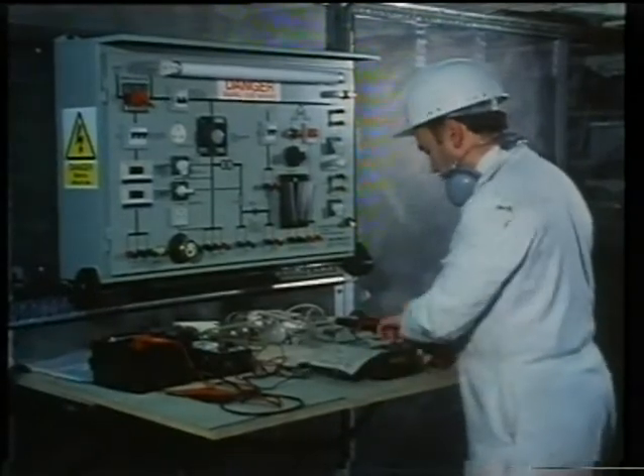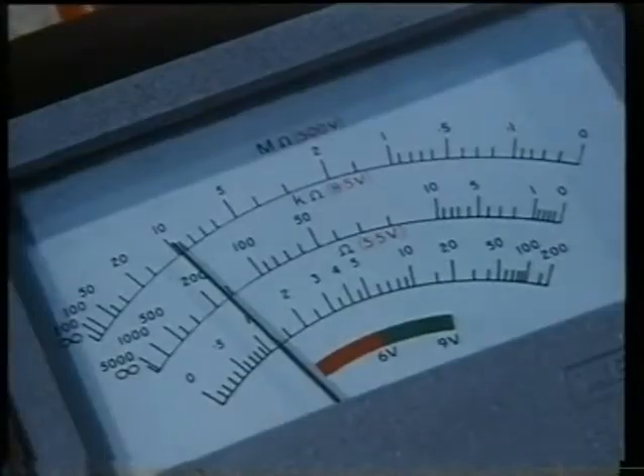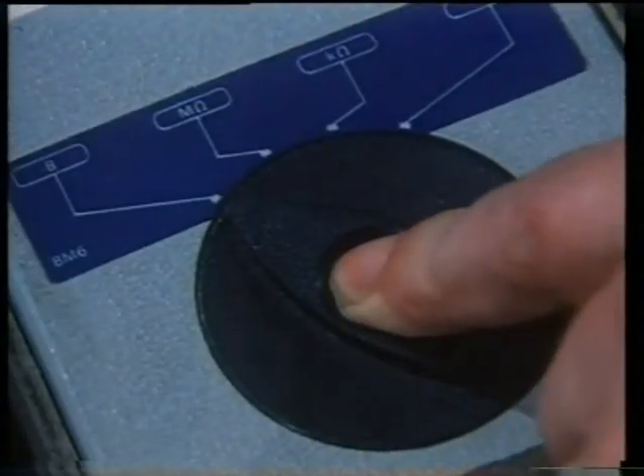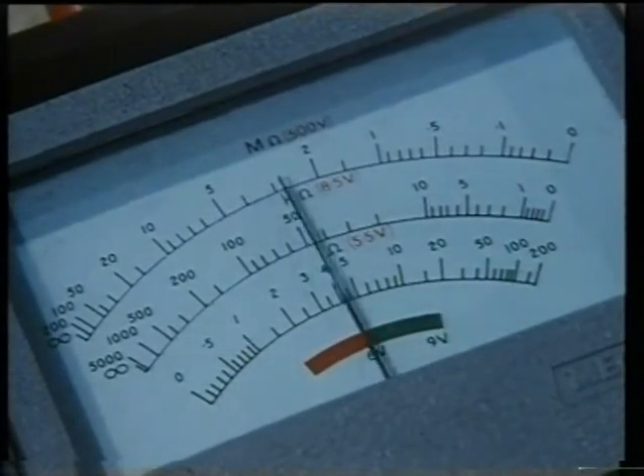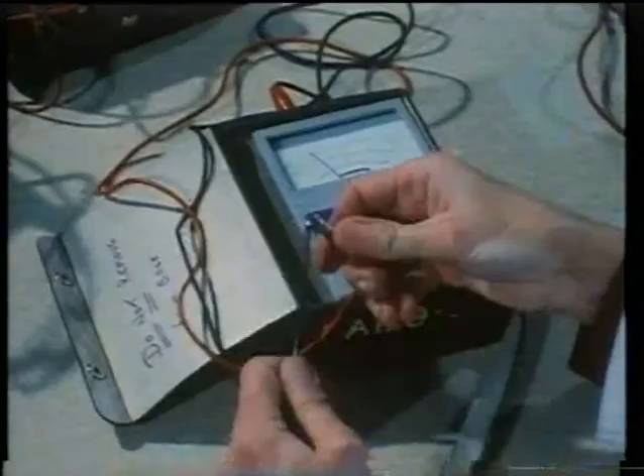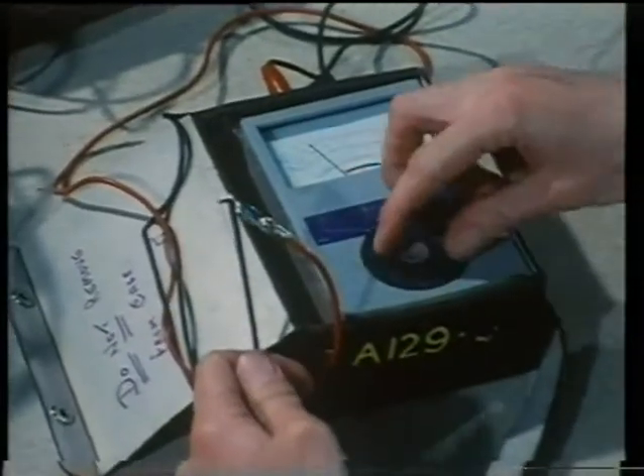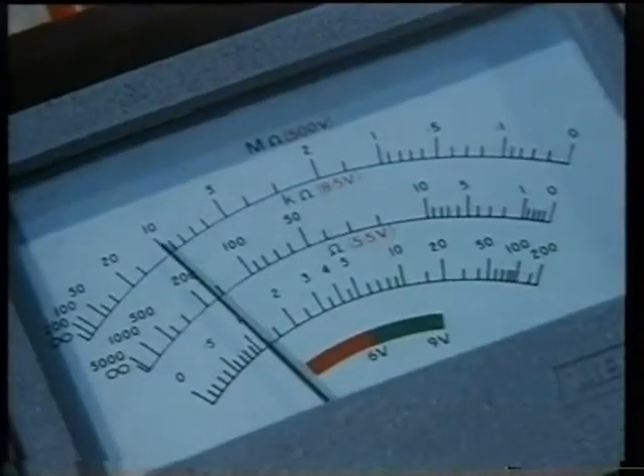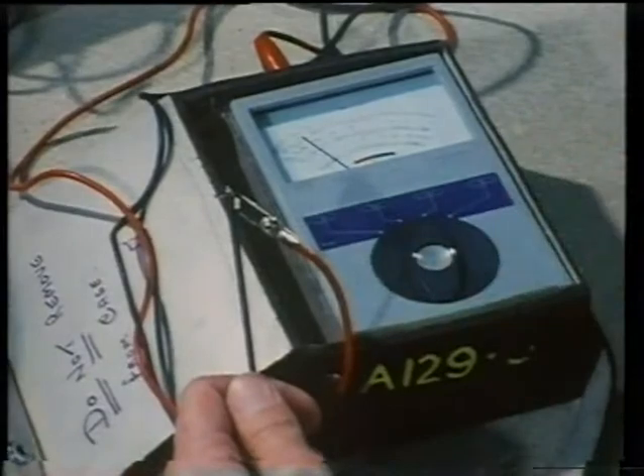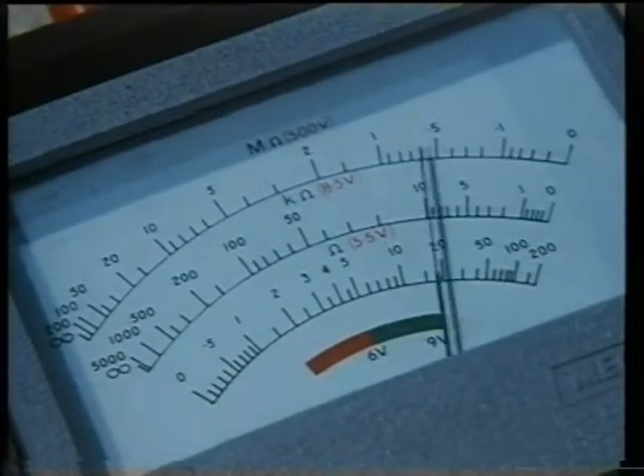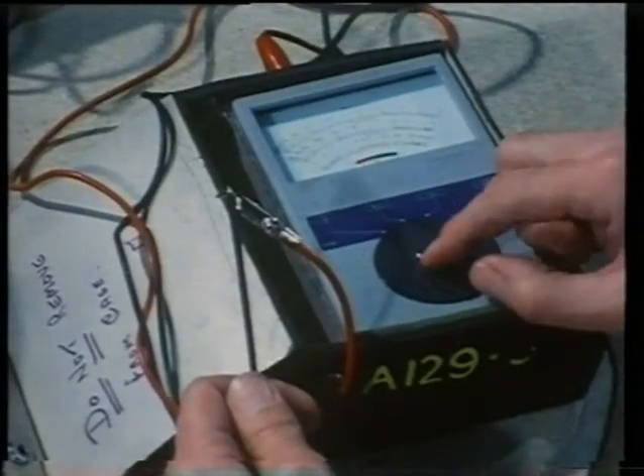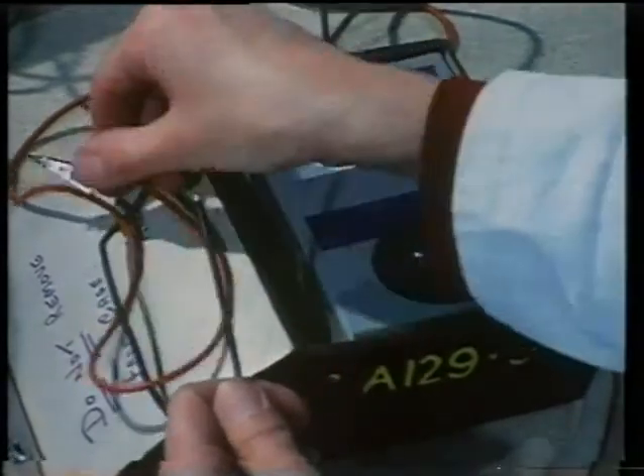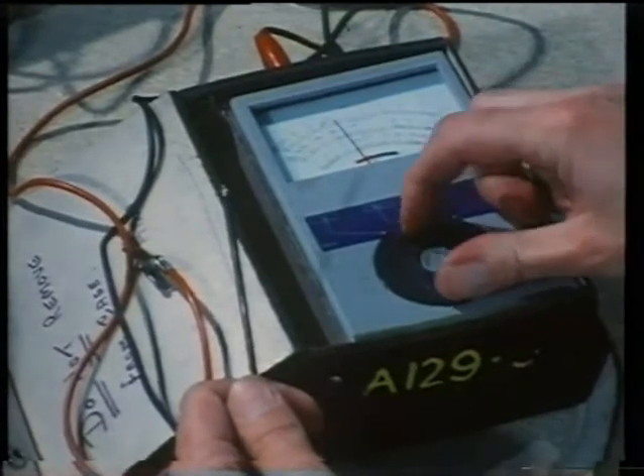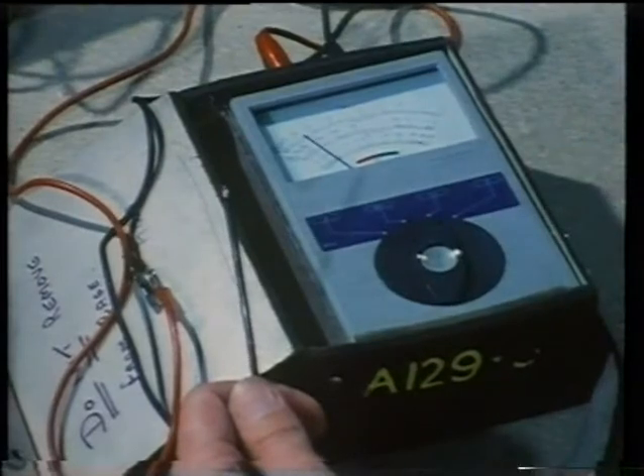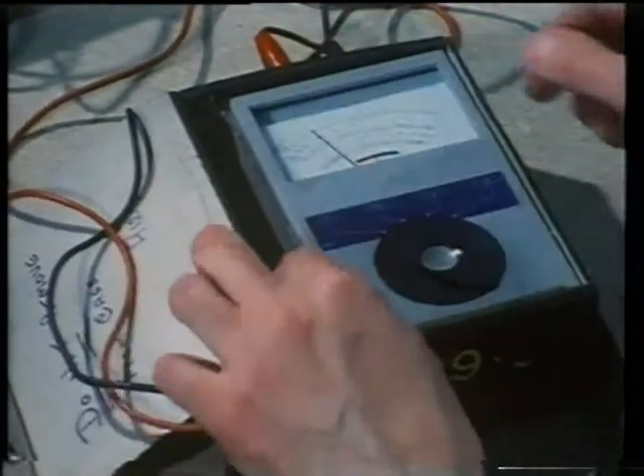An insulation resistance tester is used to monitor the condition of the electrical circuitry on board ship, as well as for fault tracing. On this particular model, there is a battery test as well as ohm, kilo ohm, and megohm scales. The meter is tested on all its scales before use by connecting the probes together, when the meter shows no resistance or closed circuit on all its scales. Then the probes are separated and the meter shows open circuit or a resistance value of infinity. Remember not to touch the probes when activating the meter. They will have 500 volts on the megohm scale, in some cases higher.